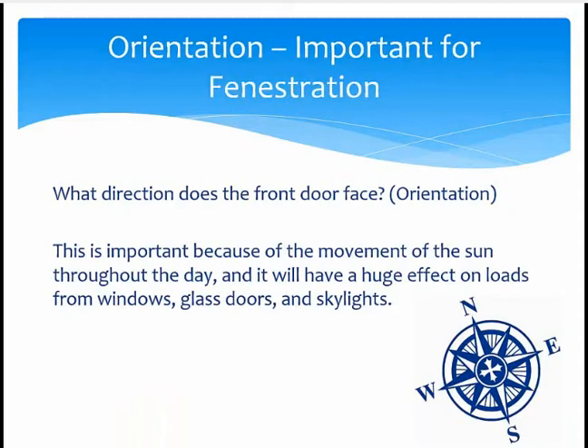There's an important consideration for fenestration, and that's the orientation of the home — that is, which way the front door faces. The direction that each piece of fenestration, each window, each skylight, each glass door faces, plays a big role in the overall load calculation because of the sun's movement across the sky throughout the day. So a west-facing window will have a bigger load than a window that faces north because we're in the northern hemisphere. Knowing which way the front door faces will help the designer get the correct heat transfer values used in the load calculation.